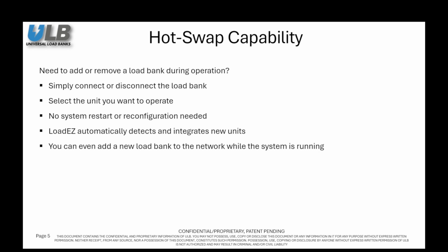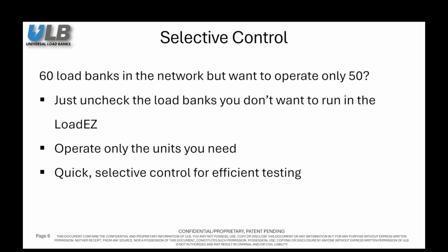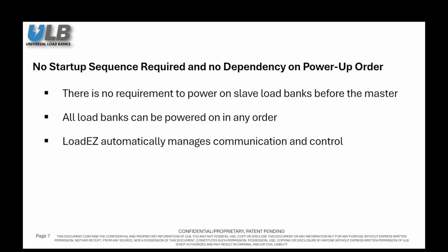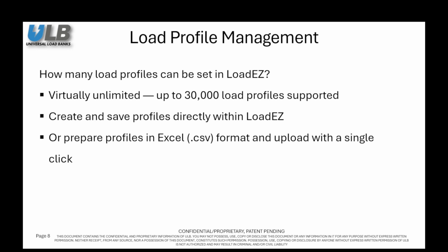LoadEZ also gives you full selective control over your connected load banks. For example, if you have 60 load banks connected but only need to operate 50, simply uncheck the ones you don't want to run. You can operate only the units you need, enabling quick and efficient testing without any unnecessary load. LoadEZ simplifies startup by eliminating any dependency on power-up order. There's no need to power on slave load banks before the master. You can power on all units in any order. LoadEZ automatically manages communication and control, making the setup process faster and more reliable.